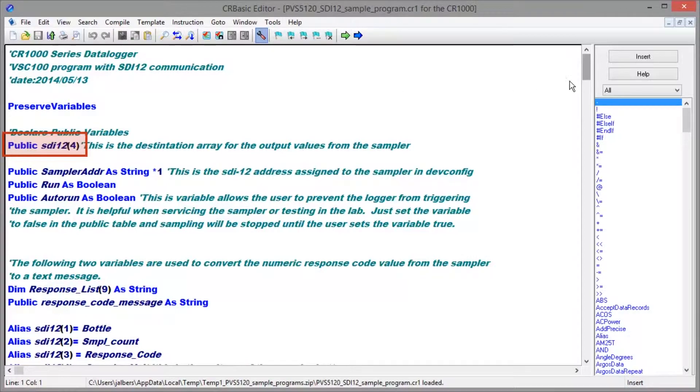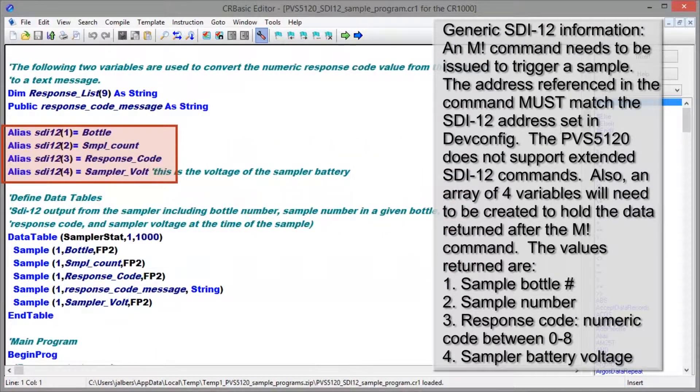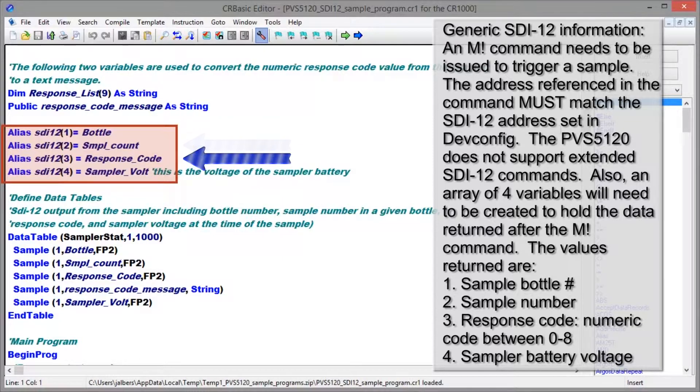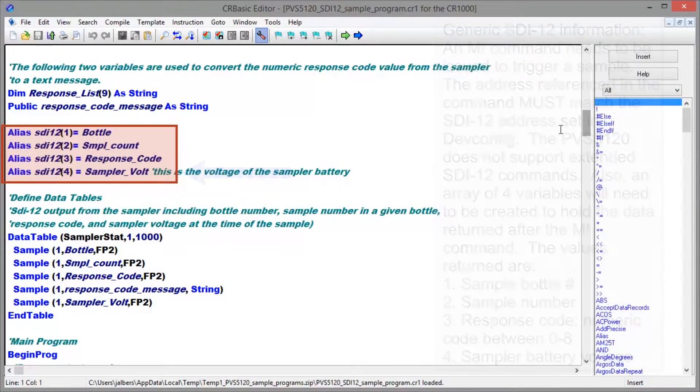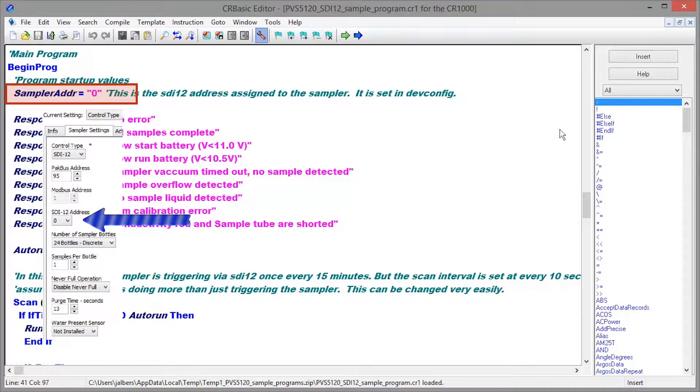In the CR basic editor, you will see an array of four variables. The values returned are sample bottle number, sample number, response code, and sampler battery voltage. We set the sampler address to zero earlier, so our program has to match that here.